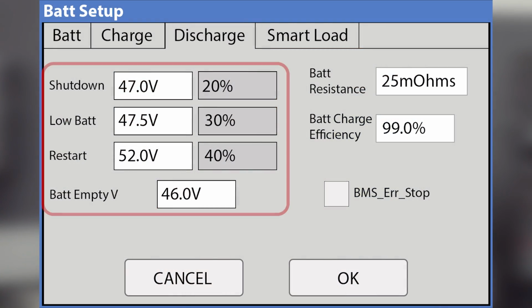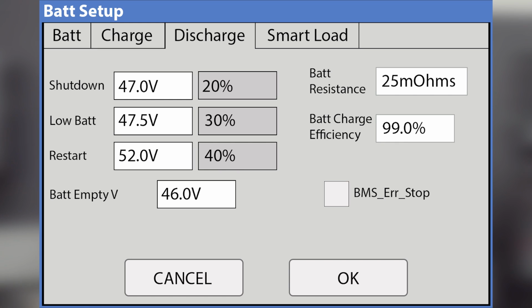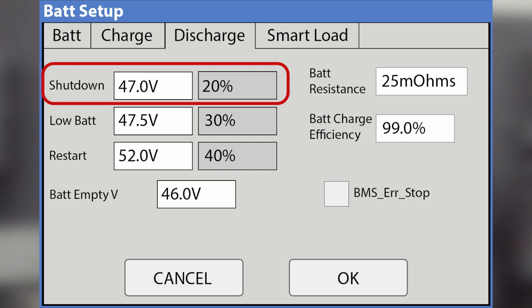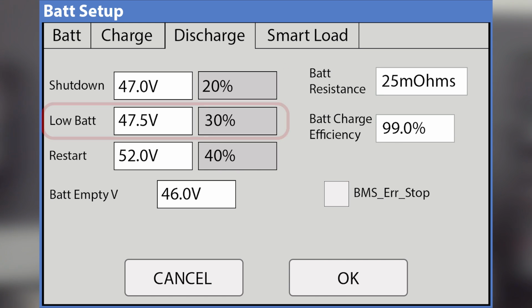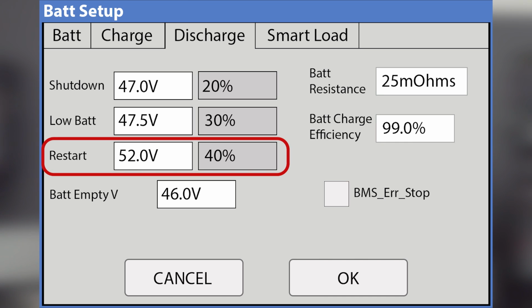Okay. These settings here on the left, we have shutdown, low battery, and restart, with a battery empty voltage at the bottom. So shutdown voltage, or percentage, is if the battery gets to that point, the inverter is going to cease AC output, so it's going to shut down. Low battery serves a couple different purposes, but it's mostly a warning. It'll make the battery icon on the front screen turn yellow, just saying, hey, your battery's getting low. It also functions as the lower boundary if you're using peak shaving mode. It won't peak shave below low battery. And then the restart voltage only comes into play if you've already hit shutdown. So if you hit shutdown, we're going to wait to turn back on until we hit the restart voltage.